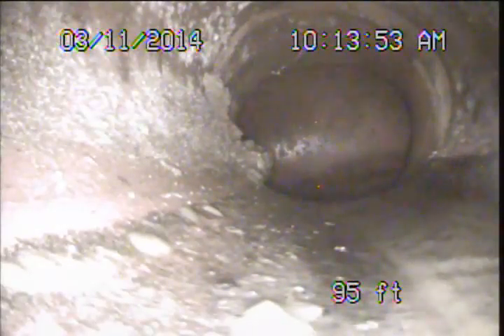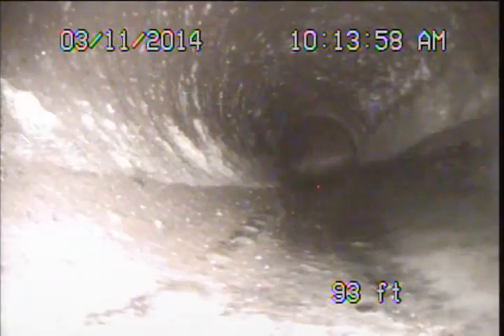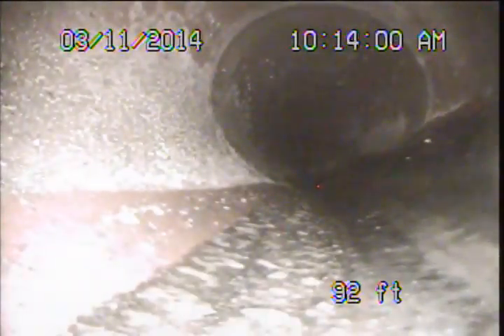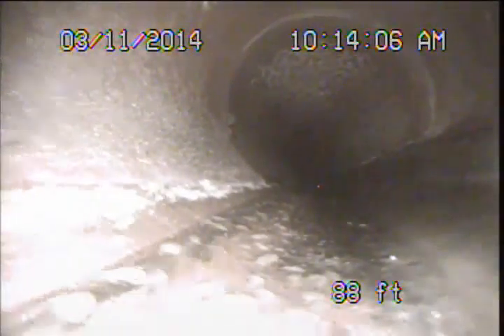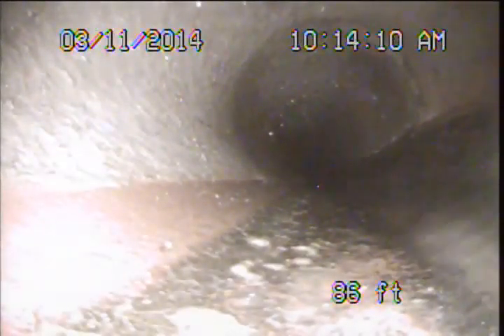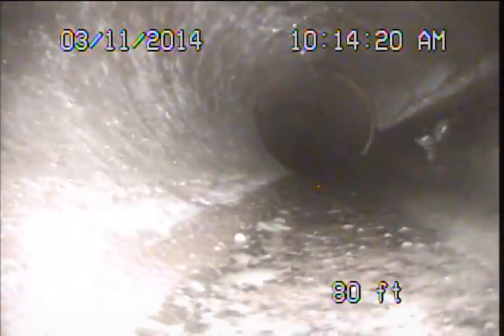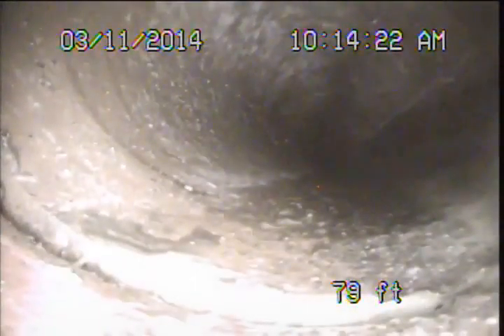As we pull off of the public sewer, we're pulling back into the original 6-inch vitrified clay lateral pipe. This is the pipe that comes from the public sewer up to the property. It's what was connected to when the property was developed. Now, these clay pipe materials are expected to have a long service life. Being a natural material, they are not expected to deteriorate underground, but they are more brittle in nature and do have a higher potential for damage during seismic activity or earthquakes.